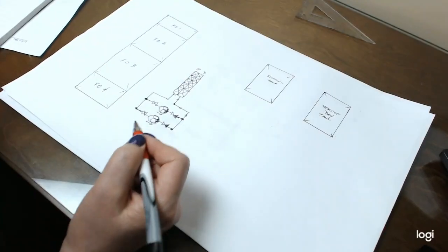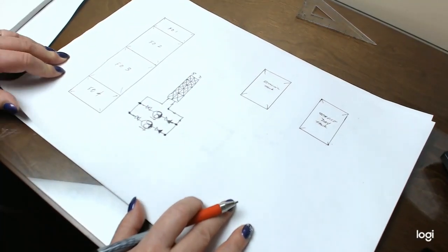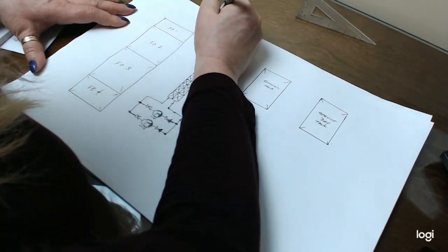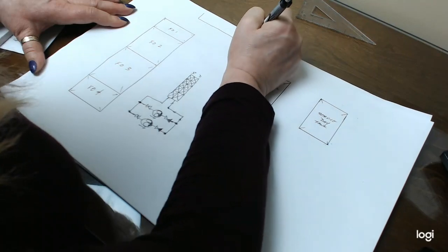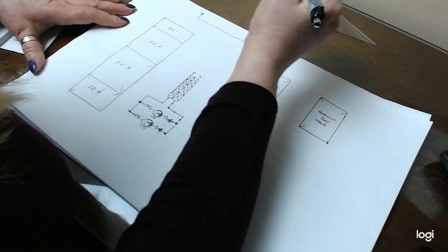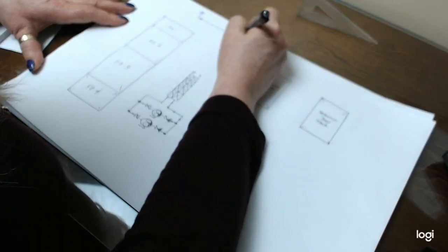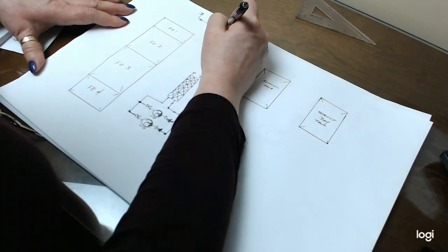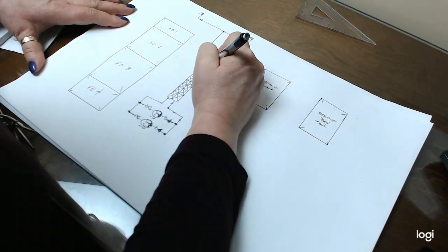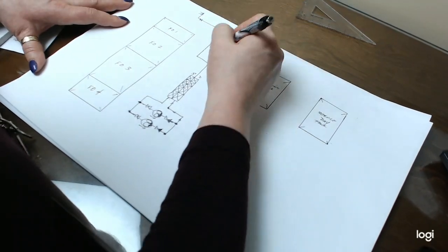Okay, so how do we get this to work? This is the basis of our fuel oil system. So what we're going to do is indicate that up here somewhere are a set of pipes that are going to be bunkering lines. Now, on the top of the bunkering lines, you would have one for port and one for starboard, so you always have two. You normally have valves to indicate which side would be open. You would have a junction, and this line would come down and it would feed directly into the manifold. So normally this would only have one direction.